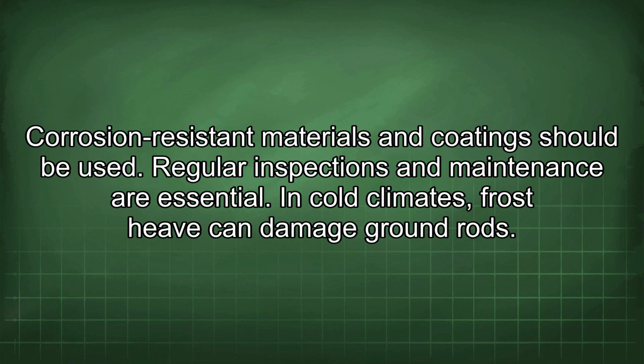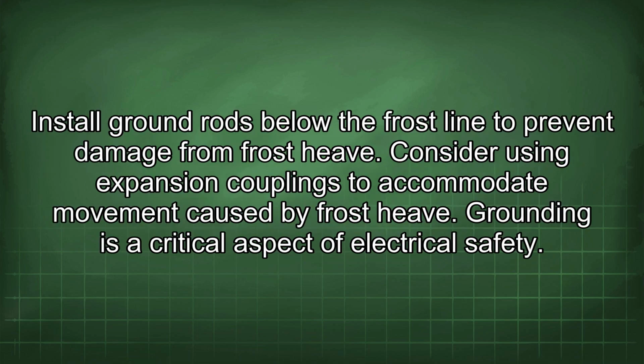In cold climates, frost heave can damage ground rods. Install ground rods below the frost line to prevent damage from frost heave. Consider using expansion couplings to accommodate movement caused by frost heave.